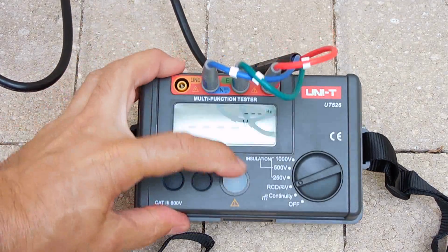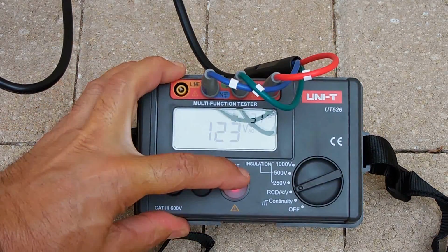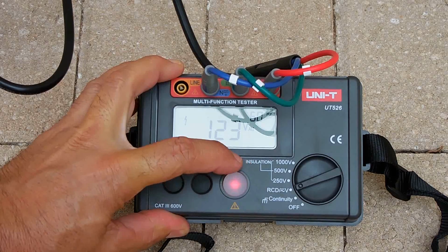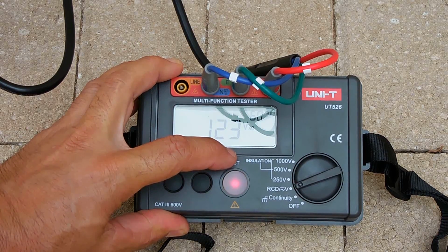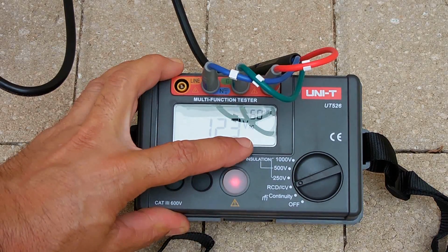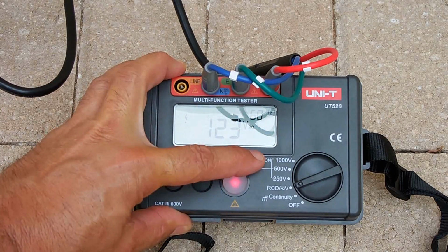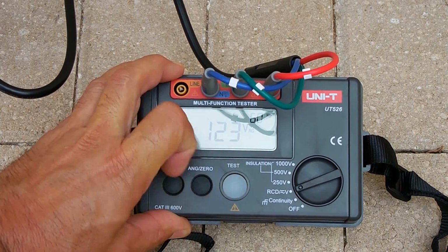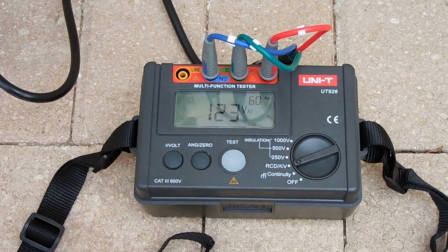And now I'm going to push the test button. And you can see over here, 123 volts. It'll automatically detect AC or DC. And there's your frequency, 60 Hertz. Push the button, power it off, and unplug the receptacle.